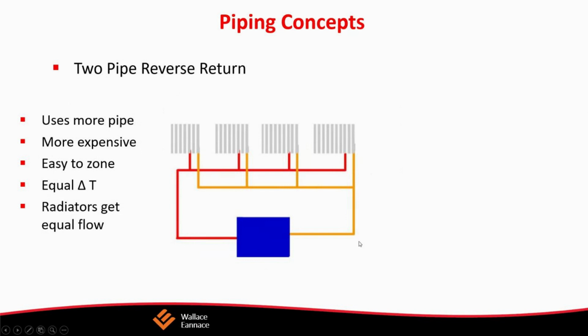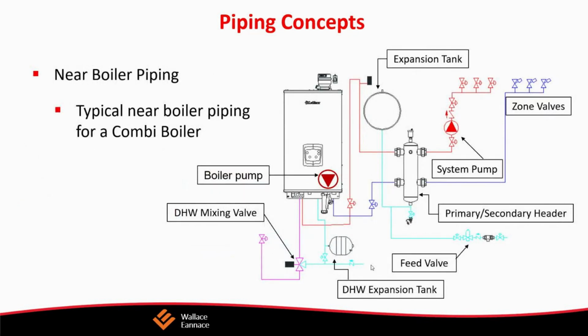How do they work? It's a Venturi tee. Very simply, the main water comes in this way, it creates a pressure drop. The water comes back from the radiator as such. That pressure drop allows the water, as you can see in this diagram here, to divert some of the water through the radiator, and the rest of the water goes straight through. This pressure restriction in here allows some of the water to route up through the radiator. It basically splits the flow. It uses more pipe. It's more expensive. But the advantage is it's easy to zone.